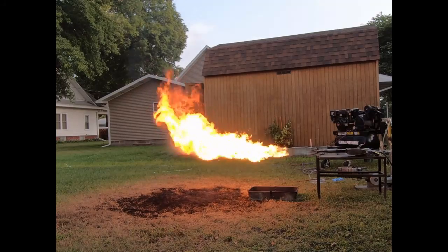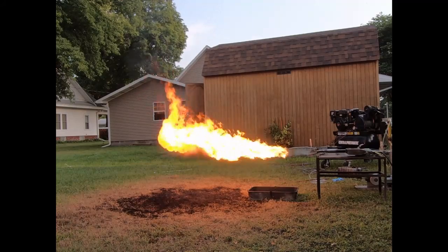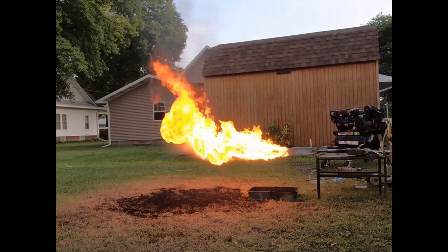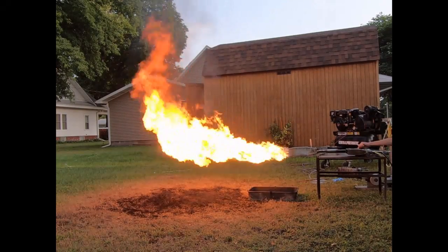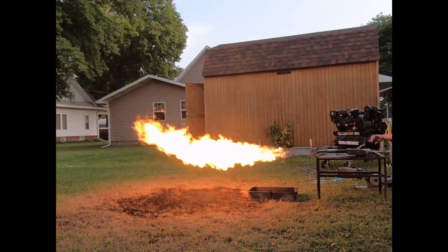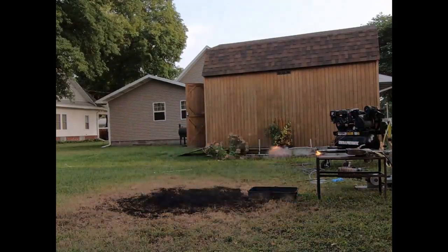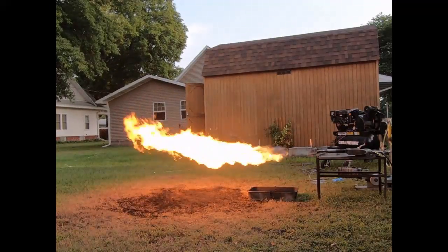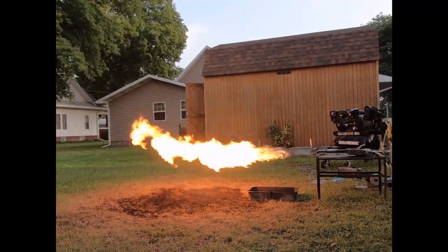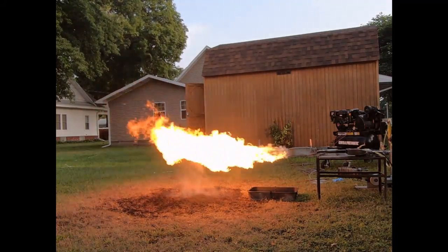But for the most part, once you get all the bubbles out of the system, all the sputtering and hiccups will kind of die down on you. It just takes a second. I like to turn the unit up as high as I can get it. There's some more air bubbles there — see how it kind of sputtered? Some burners will actually go out because of that. I'm actually excited to see that this thing didn't go out.